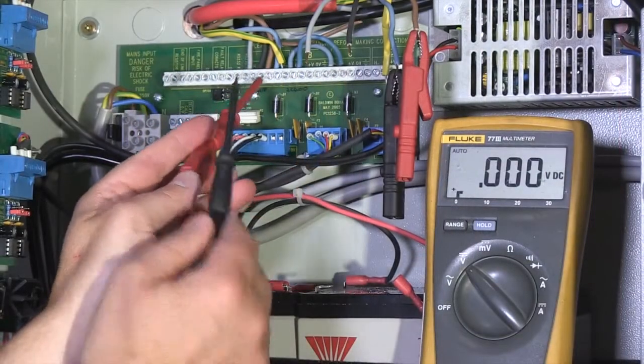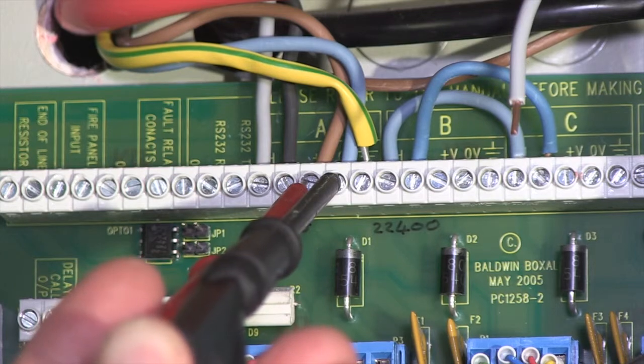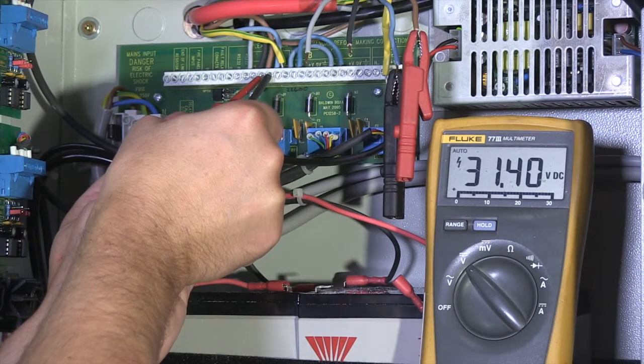The voltage between the 0 volts and plus volts at the A circuit terminals should be between 29 volts and 35 volts DC.